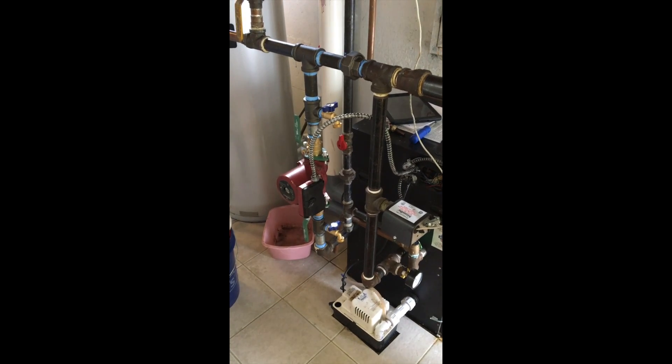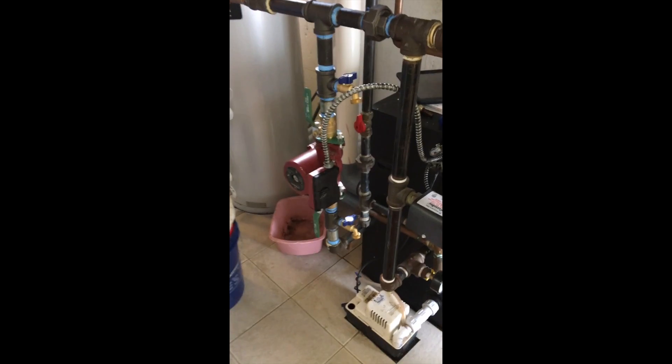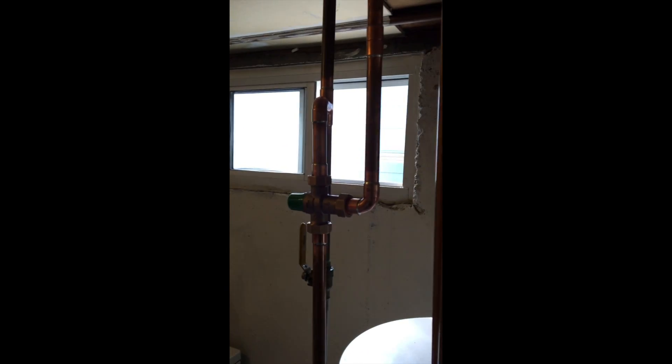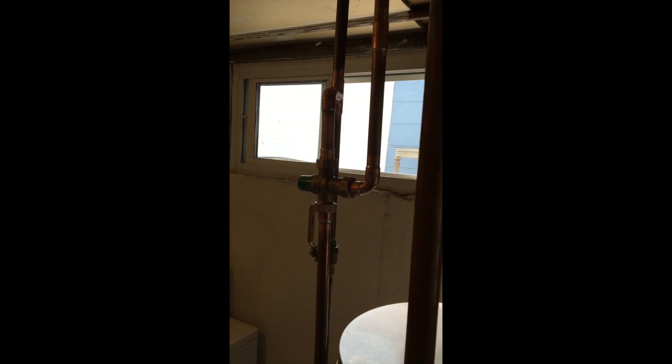All right, we've completed the primary loop with the primary loop circulator wired to the red wire and neutral on this original Burnham Alpine boiler. We purged all the zones. We installed the mixing valve in domestic water, and purged all the zones.